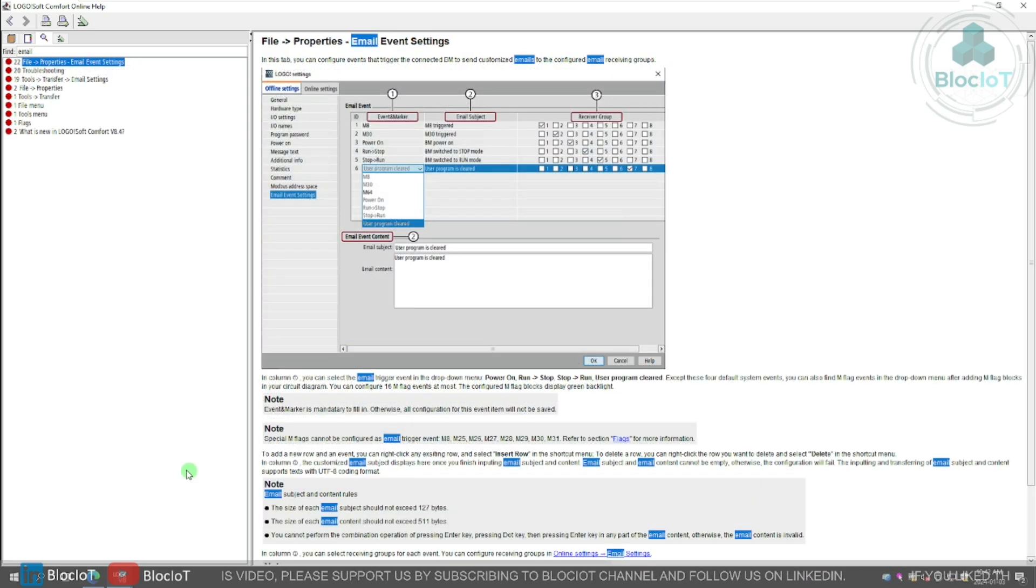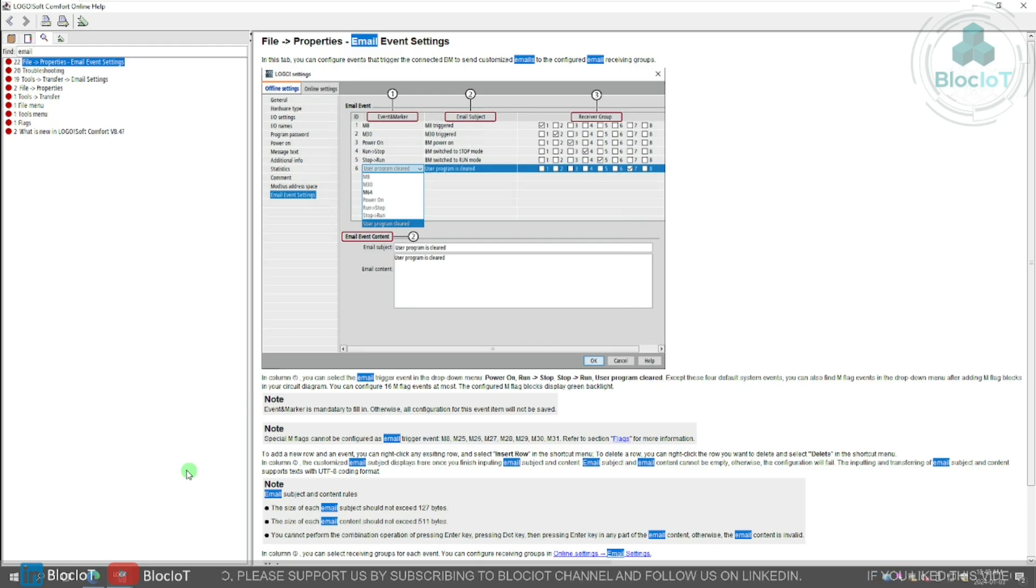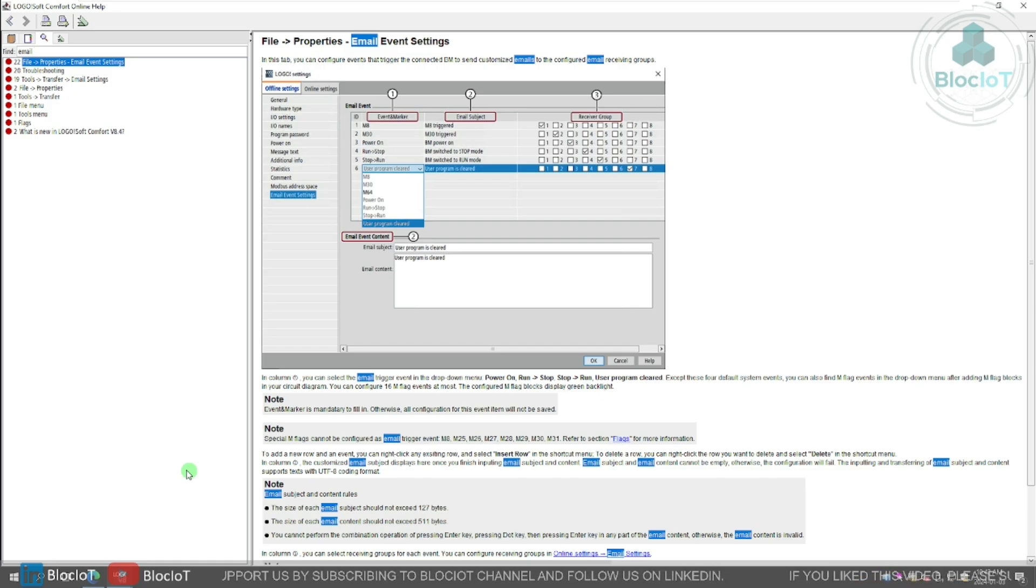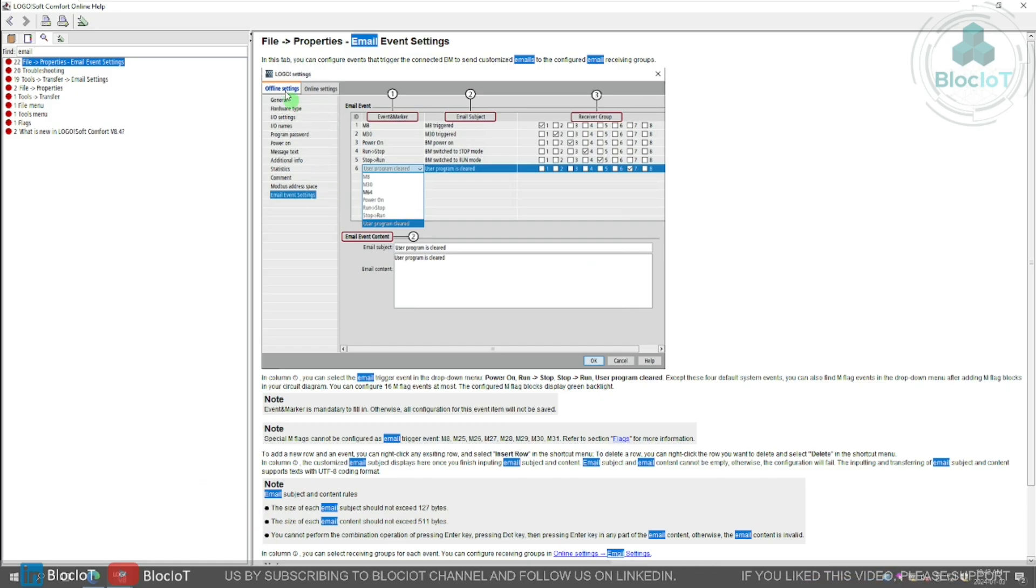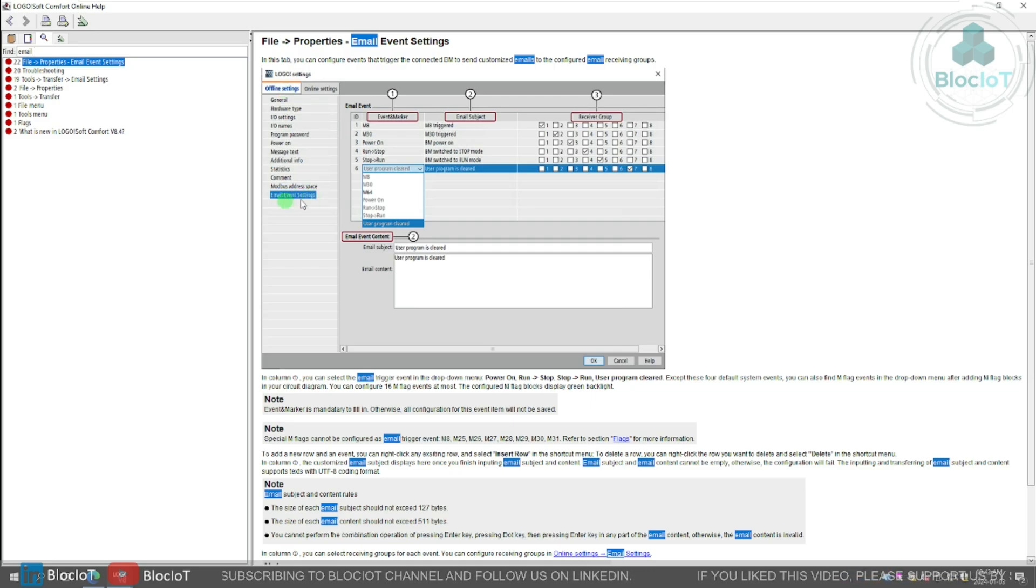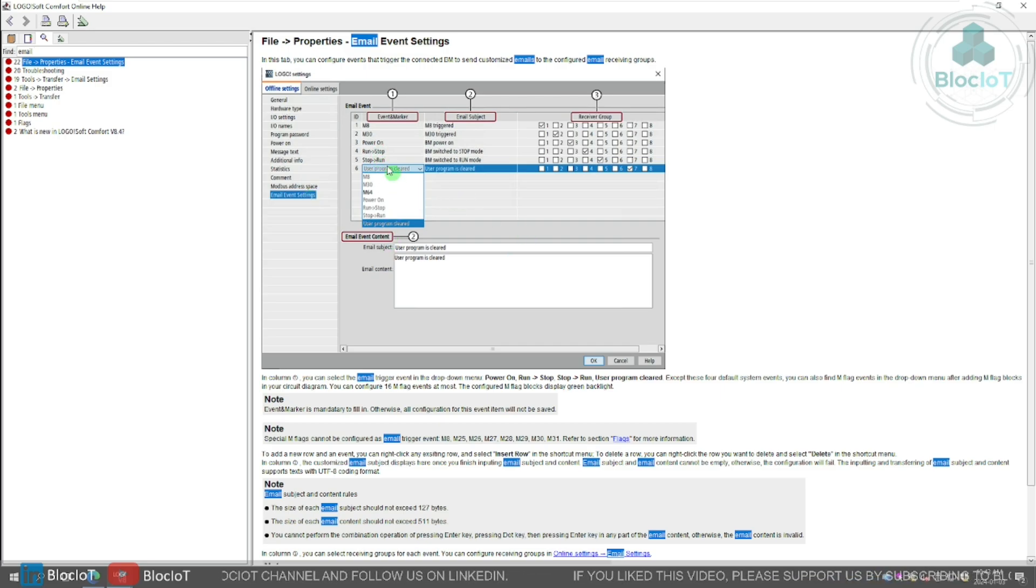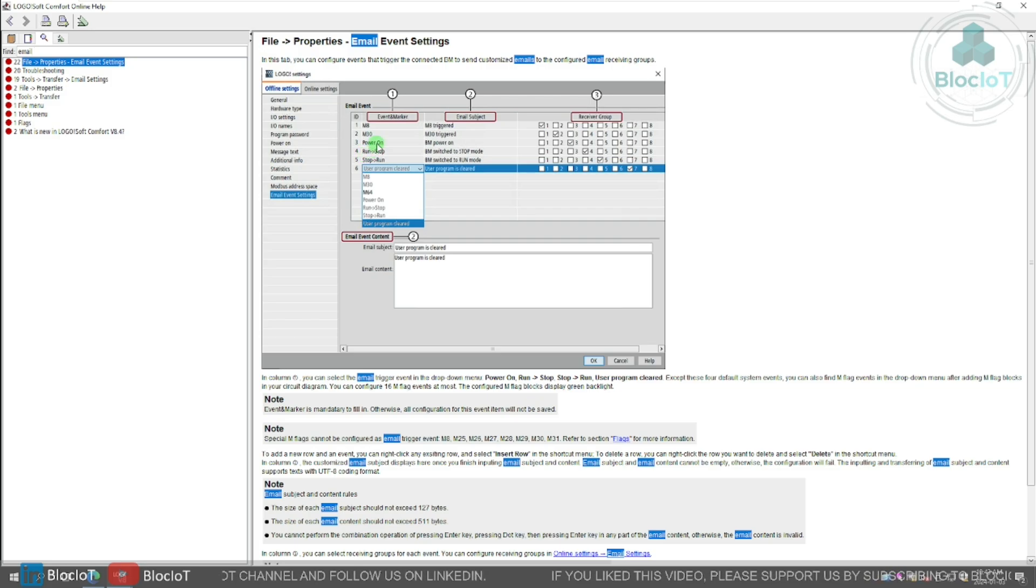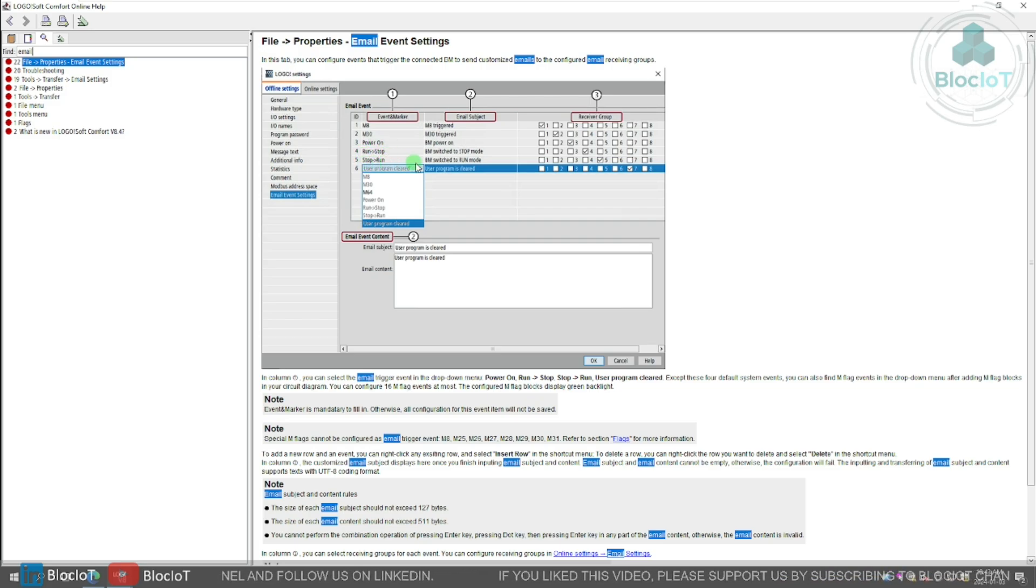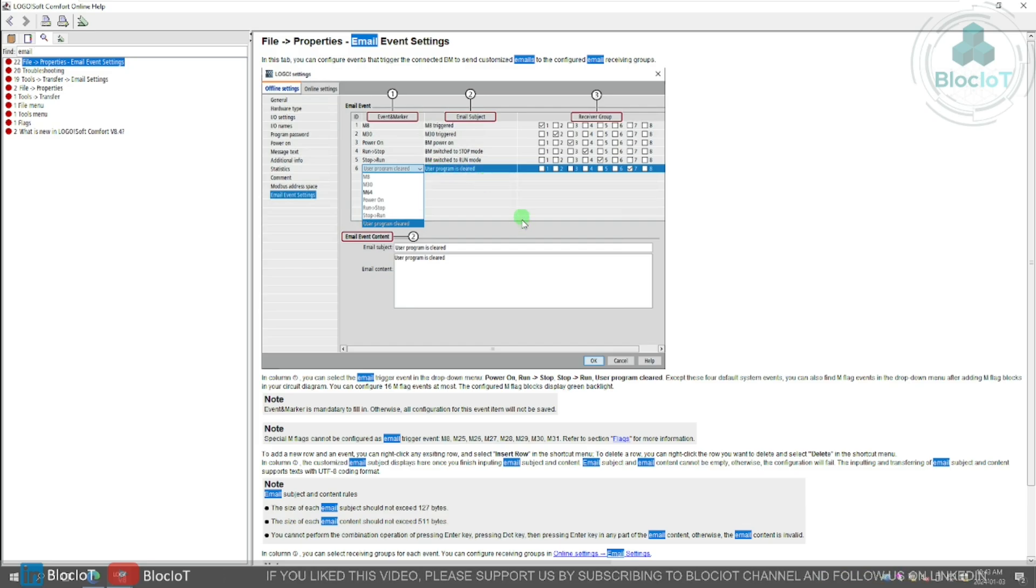Next great new feature is sending customized email to configured recipients with trigger. This is a very neat feature which was not available in logo, but right now you can just go to your offline setting, and there is a new option for emails event setting. And as you can see here, for example, you can define different triggers for when your logo is powered on, or when the logo is turned from run to stop, or stop to run.